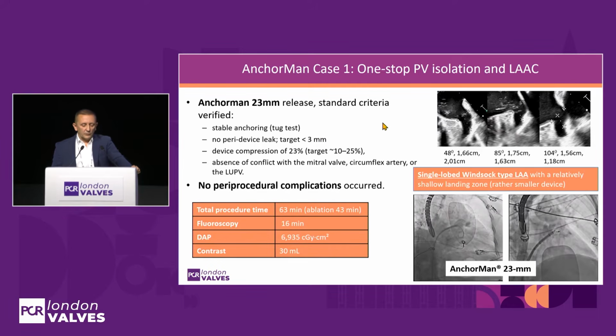So as you can see on the right side, this is single-lobed windsock type LAA with a relatively shallow landing zone. The average diameter made at different angles by TEE was between 1.6 to 1.7, but with a maximal depth of 2 centimeters. For this particular case, we selected Anchorman 23. After releasing, we used the standard criteria for device success. We achieved a stable anchoring by tug test.